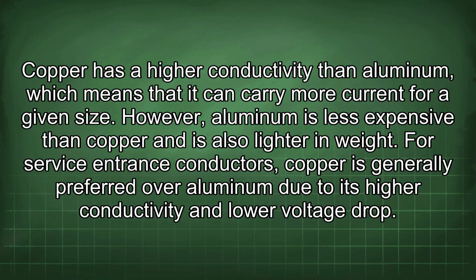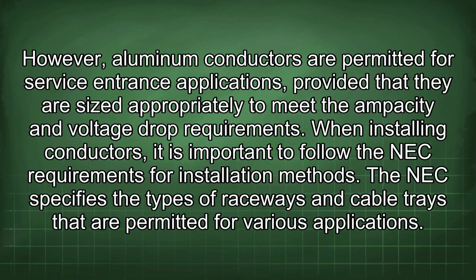For service entrance conductors, copper is generally preferred over aluminum due to its higher conductivity and lower voltage drop. However, aluminum conductors are permitted for service entrance applications, provided that they are sized appropriately to meet the ampacity and voltage drop requirements. When installing conductors, it is important to follow the NEC requirements for installation methods.